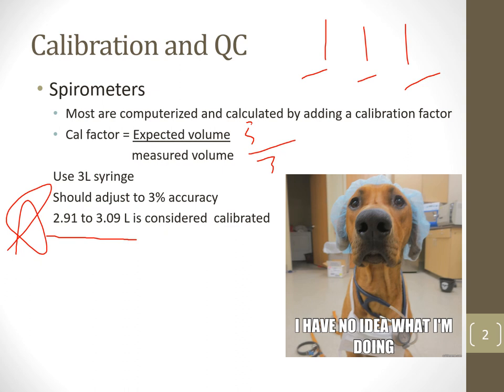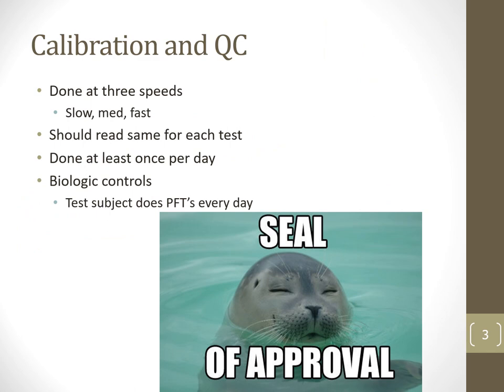So every day the PFT equipment is used, we have to calibrate it. We go in at the beginning of the day and do at least a flow test with the 3-liter super syringe—slow, medium, fast—to show it's within calibration and accurate, so the values we get are reliable. That's why it's important: we want to make sure our patients get the right diagnosis, the right severity assessment, and the right medication process for their disease. Three speeds—slow, medium, and fast—should give the same readout each time, as long as user error isn't involved. You want to do this at least once a day that the equipment is being used.